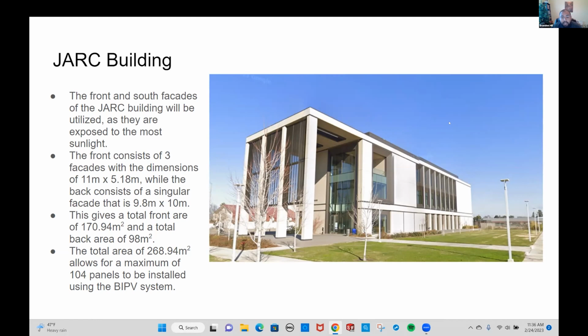The front side of the building consists of 3 facades, 11 meters by 5.18 meters. The back side has a singular facade that is 9.8 meters by 10 meters. This gives us a total usable area of 268.94 square meters, which allows for a maximum of 104 panels to be installed using the BIPV system.